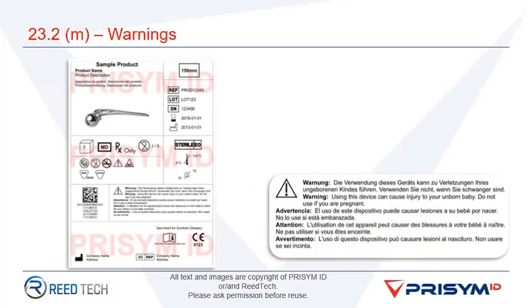Now, depending on the device you manufacture, this section here, 23.2M, could be one of the biggest changes that will impact your label. It's not only the additional space requirements that including these warnings will have, but also the translation handling that you need to go behind that to support that. The label must now include any warnings or precautions that need to be brought to the immediate attention of the user. Now, manufacturers may consider what these warnings and precautions are and whether they need to go on the label or can be just covered on the IFU.